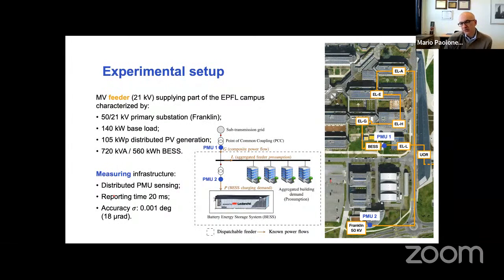And we equipped this feeder with a phasor measurement unit infrastructure. We have PMUs in all the buildings, but the PMUs that we use are located here on the low voltage side of the battery, so essentially on the AC terminals of the converter, and in correspondence of the point of common coupling with the external grid. So these are the two PMUs that I'm referring to in what follows. These PMUs have been developed by my laboratory. They are compliant with the IEEE C37.118 standard. They have a reporting rate that in this experiment was 20 milliseconds.